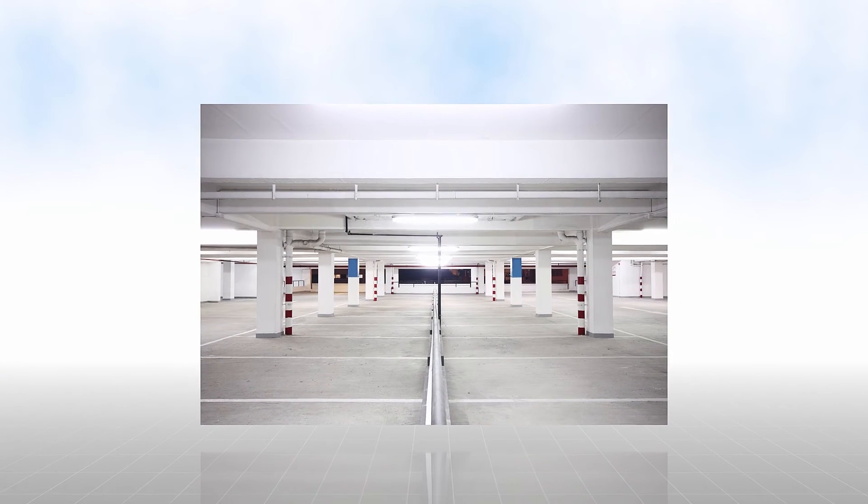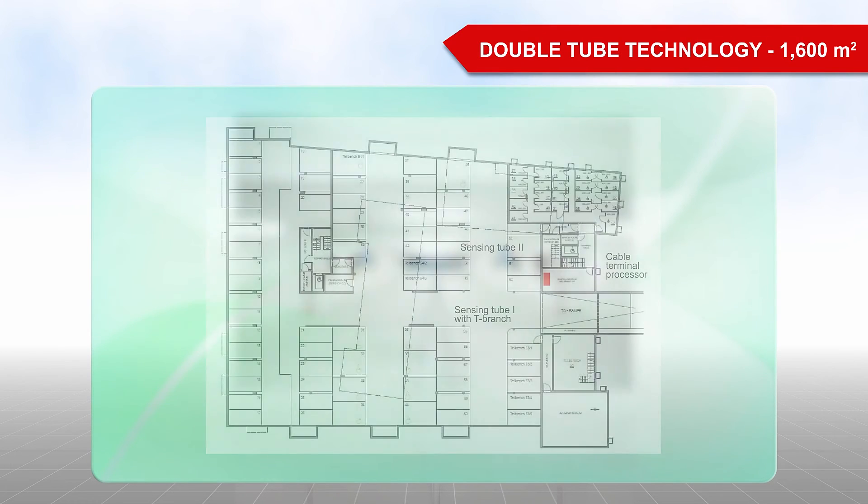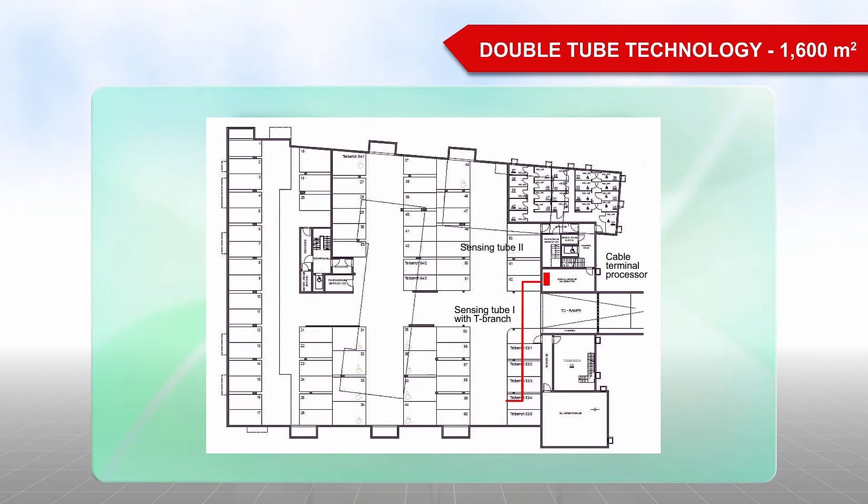Two sensing tubes can be connected to the ADW535, which is known as double tube technology. This means that an area of up to 1,600 square meters can be monitored with one cable terminal processor.